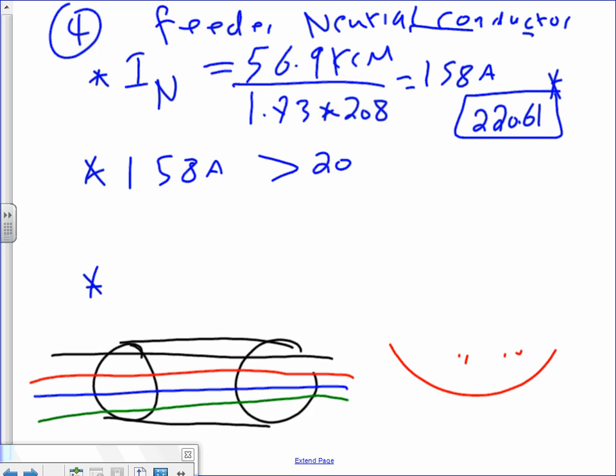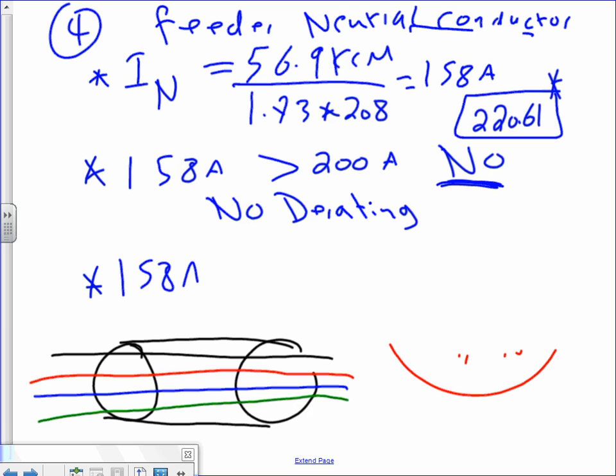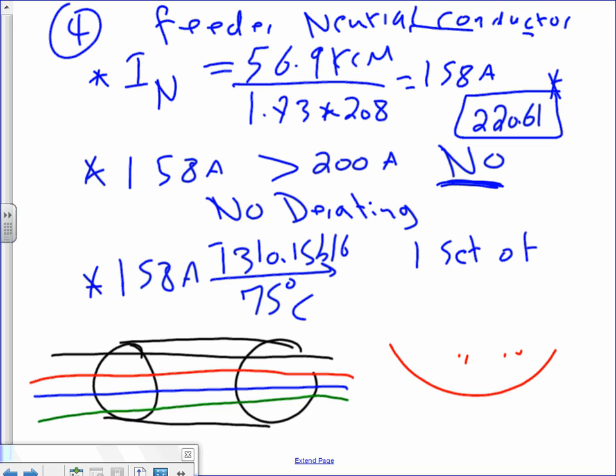Is it more than 200 amps? No. Do I need to derate the 70% that we did for the neutral? No, so I don't need to derate. No derating. Then you take 158 amps, gentlemen. Take it to table 310.15 B16, 75-degree column, and that will get you one set of one conductor, 2 aught AWG THHN.